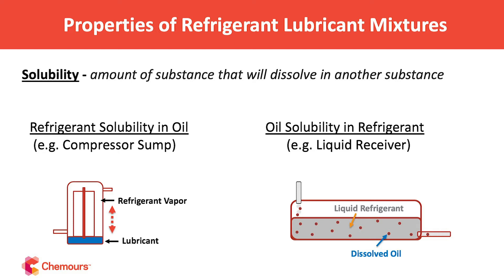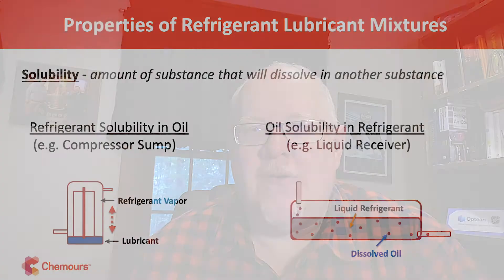On the other side, in something like a liquid receiver — which is mainly bulk refrigerant — there is some entrained oil circulating in the system that gets into the receiver and interacts with the bulk liquid refrigerant. So how much of that oil dissolves in the bulk refrigerant matters, because it can then be transported out of the receiver and back to the compressor. It's important to understand solubility from both perspectives.